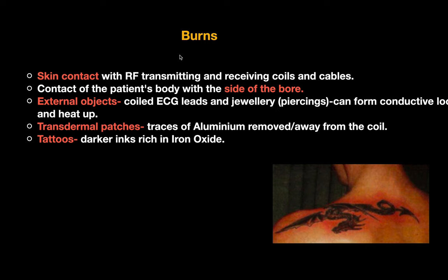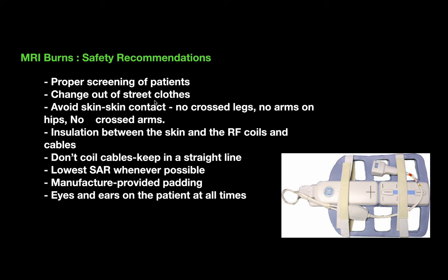Burns can be caused by skin contact with RF transmitting and receiving coils and cables, patient body contact with the bore, and external objects like coiled ECG leads and jewelry forming conductive loops. Transdermal patches containing traces of aluminium should be removed or kept away from the coil, and tattoos containing iron oxide may also cause burns. Safety recommendations include proper patient screening, providing gowns, avoiding skin-to-skin contact, no crossed legs or arms on hips, insulation between skin and RF coil, keeping cables straight, using the lowest possible SAR, and monitoring eyes and ears at all times.